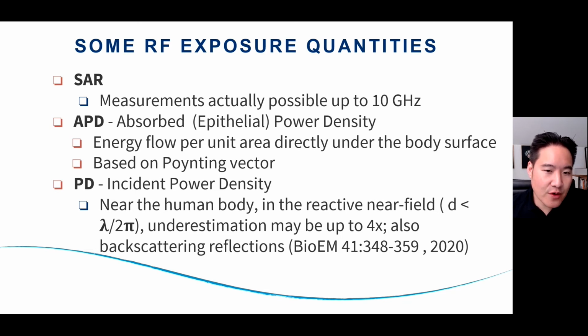And PD is short for incident power density, which could be IPD, or often just referred to as just power density. And something to point out here as far as the problem with PD is that the value is underestimated when quantities are considered near the human body due to the reactive near field effects. And according to a BioEM paper, when you go farther, there's also backscattering effects, which are caused by reflections from the body and the device that can occur as well.